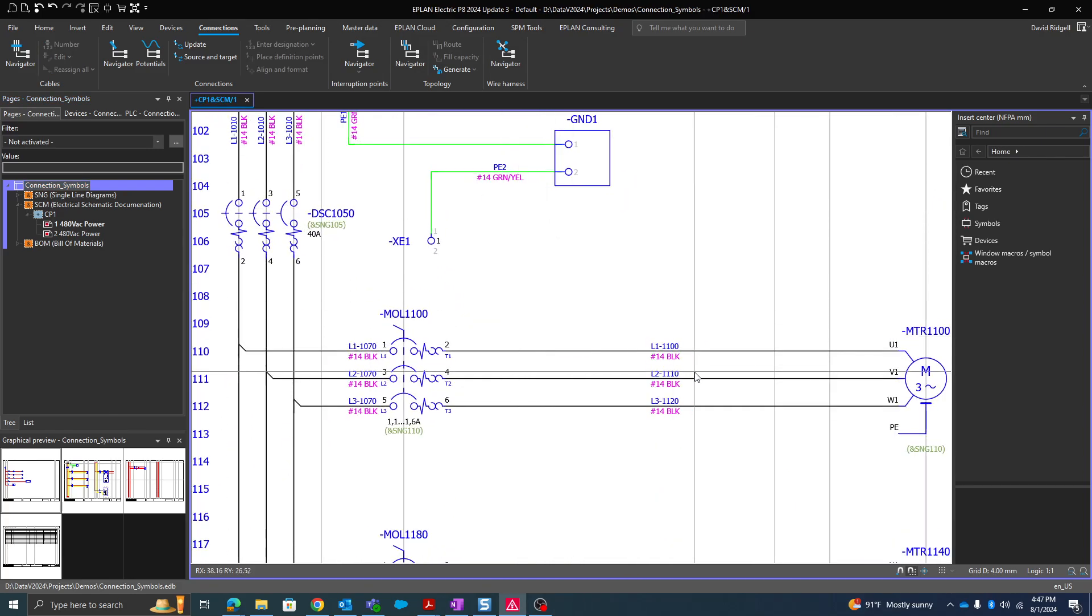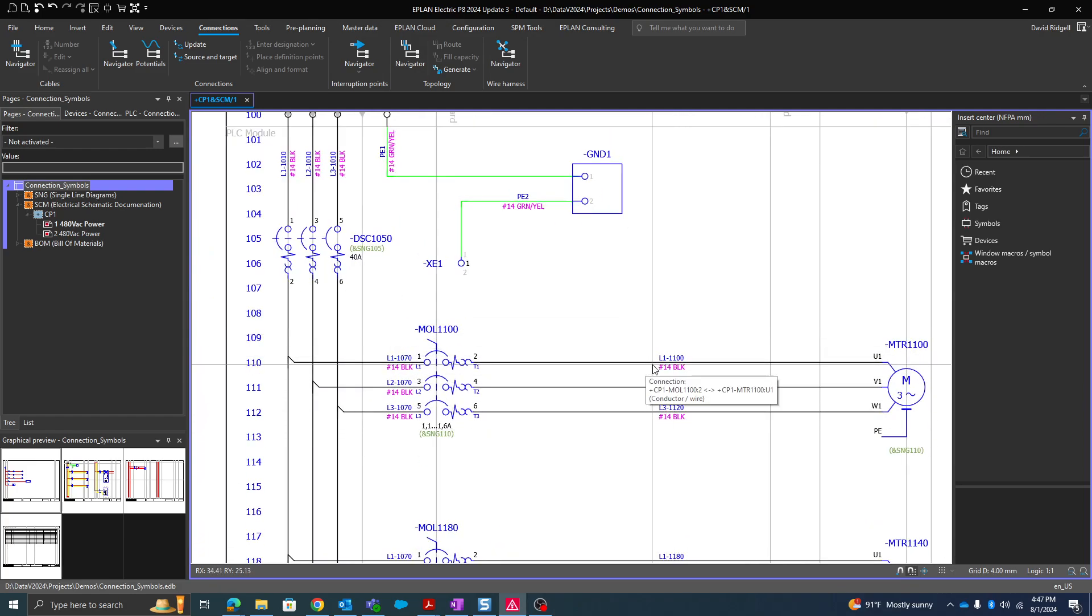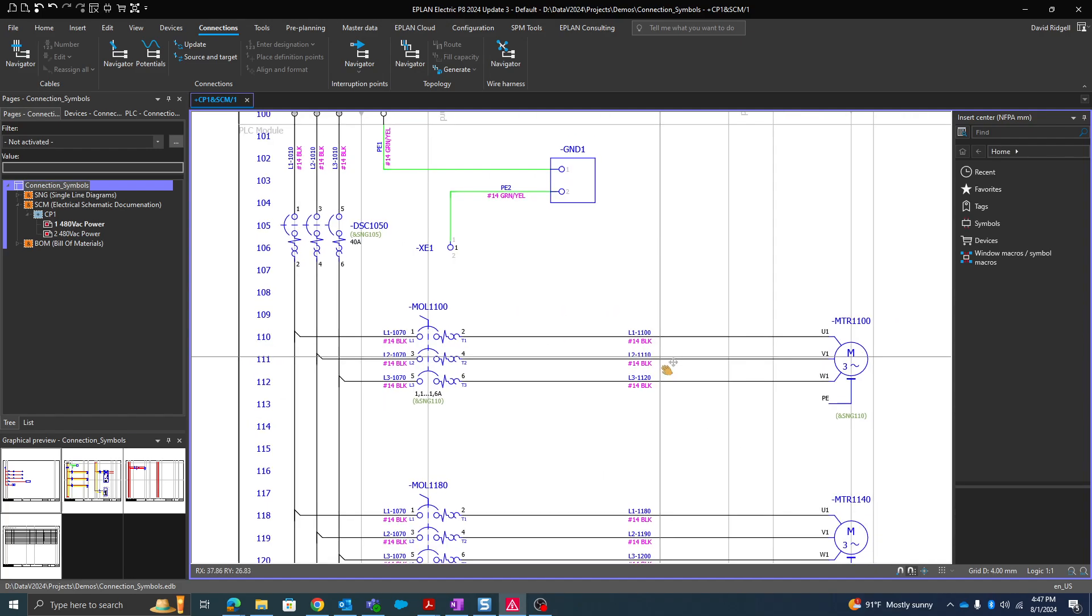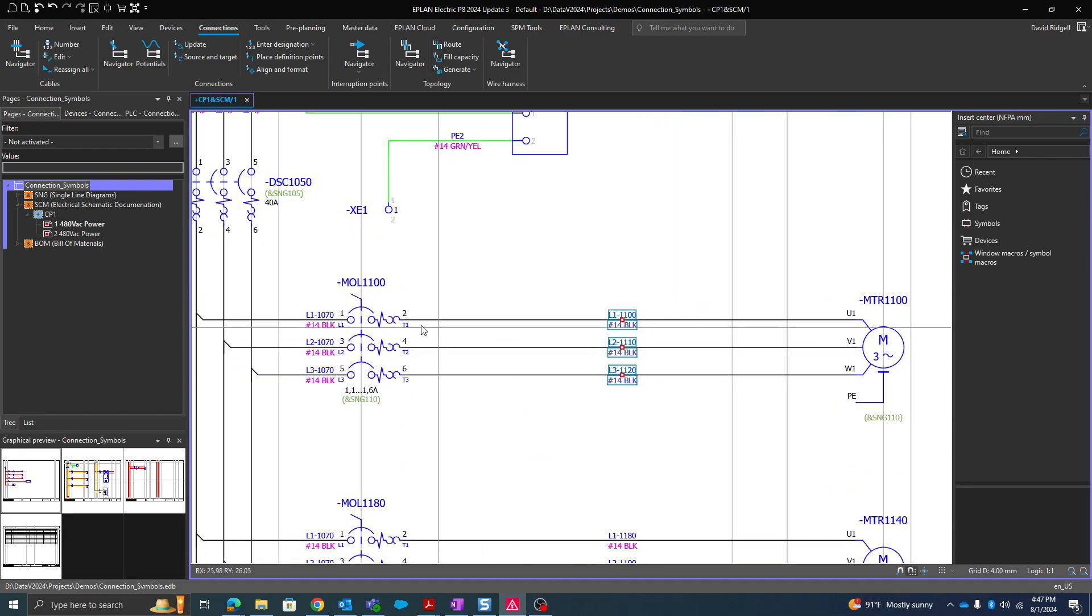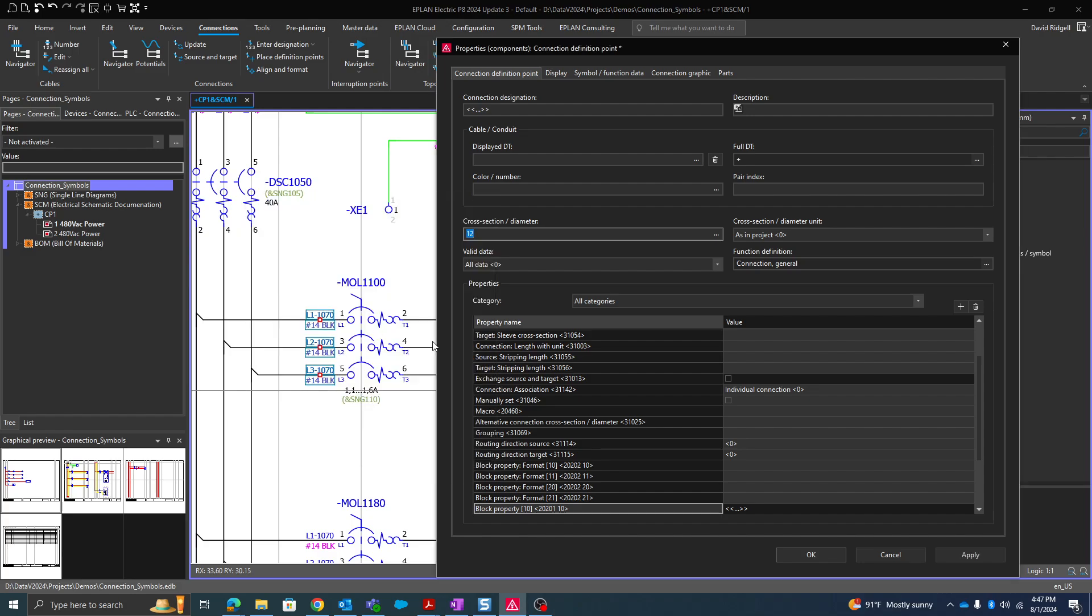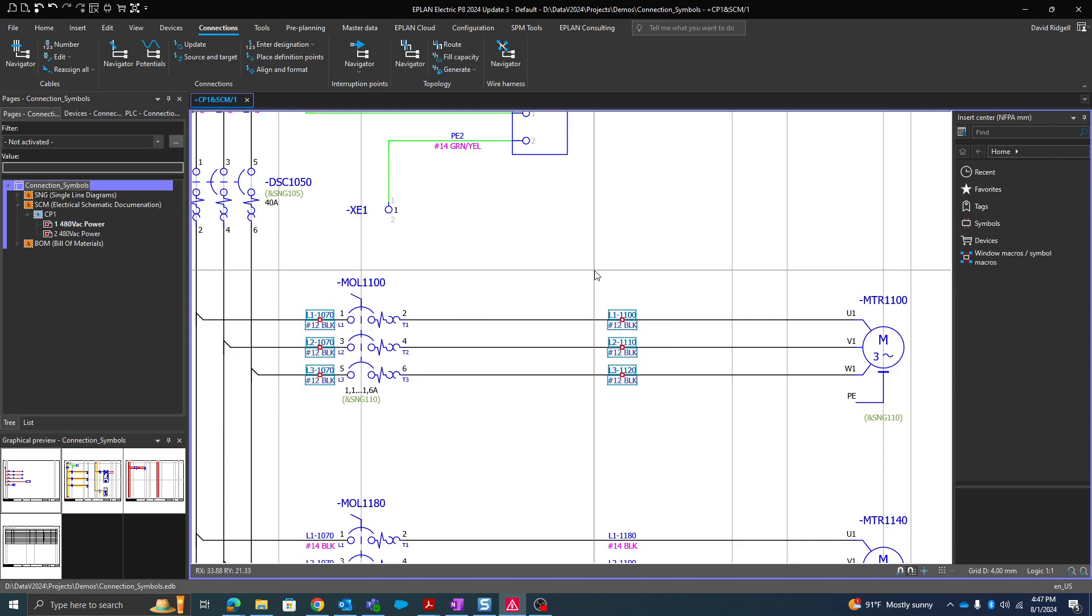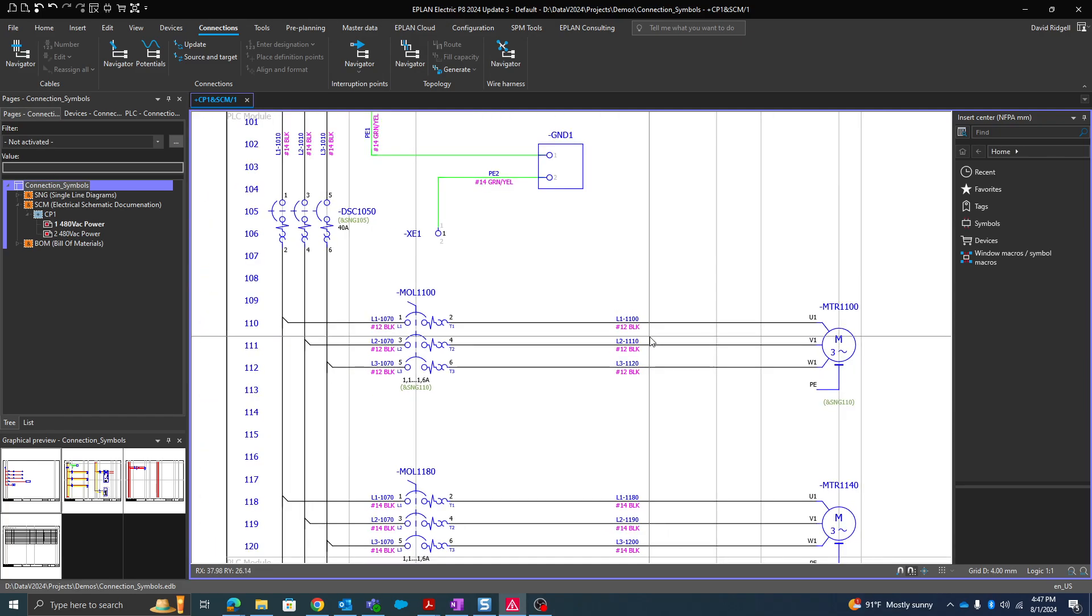Before I go into that, often a question comes up about this. That's great, but what if I want a different wire size for a particular section? That's not a problem. We can go into the properties of these connection definition points. Then here we can define the cross-section diameter as 12, for example, and then I'll update my connections. And now that will show. So our connection definition points definitely take the highest priority.